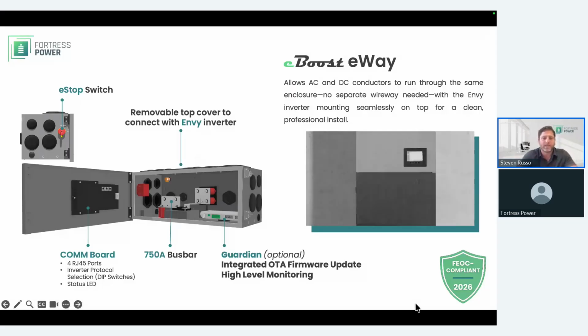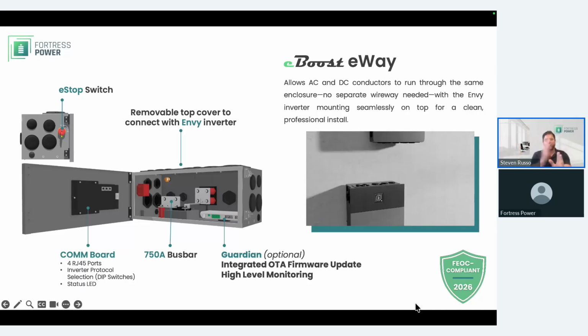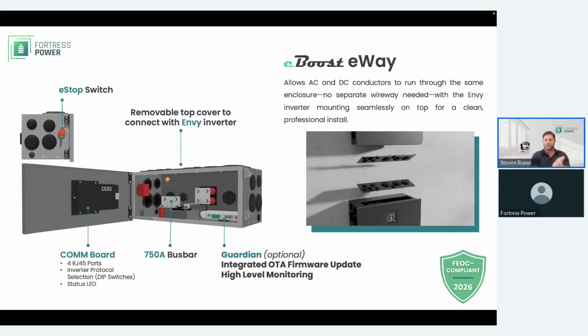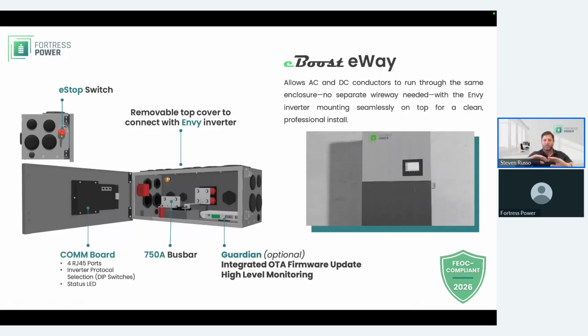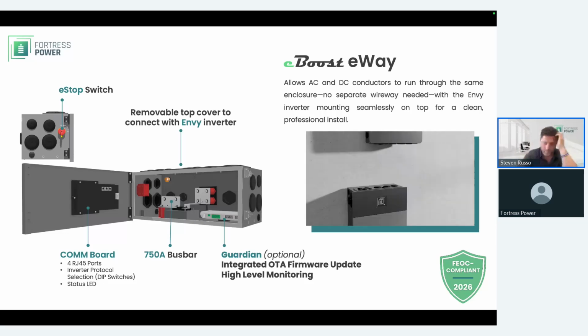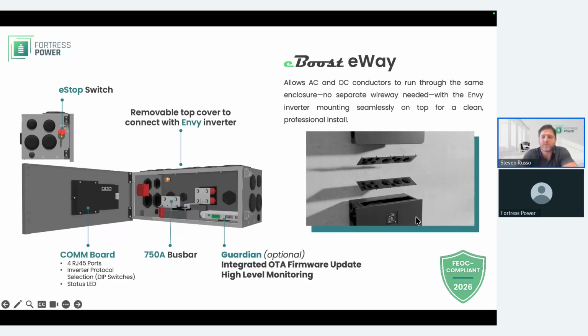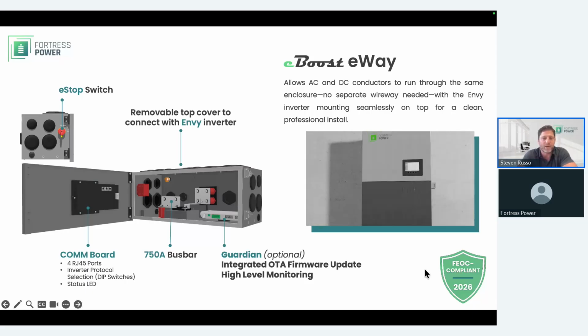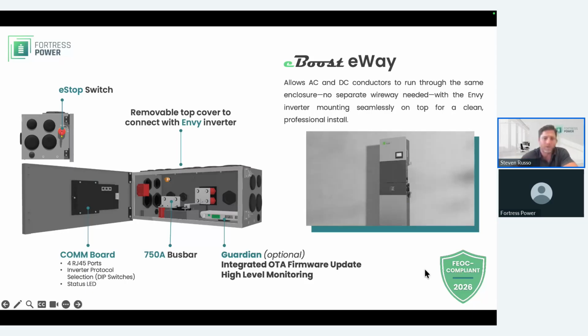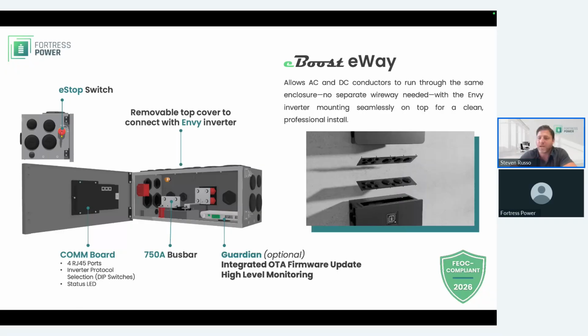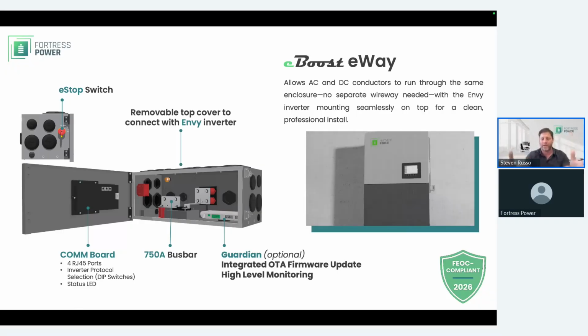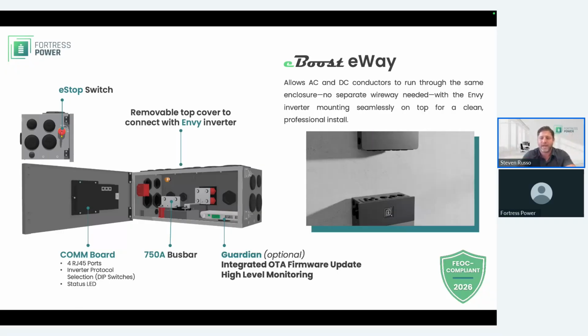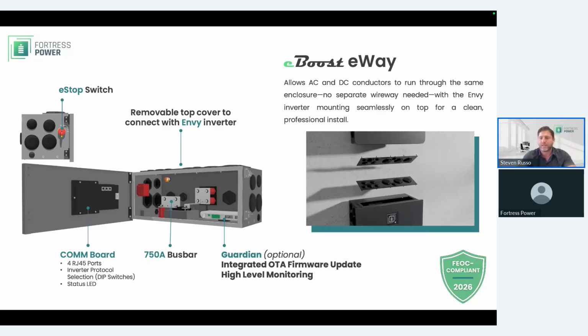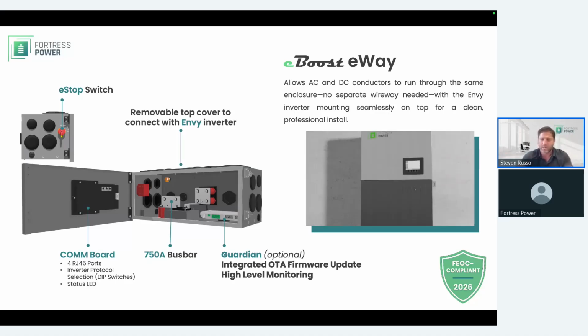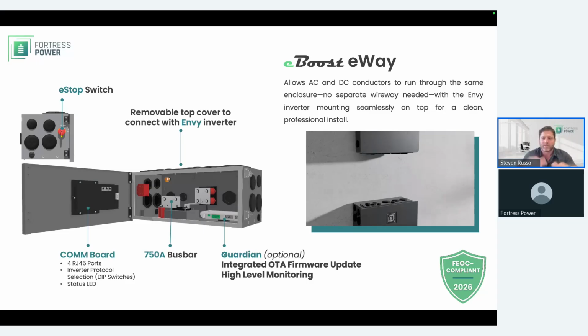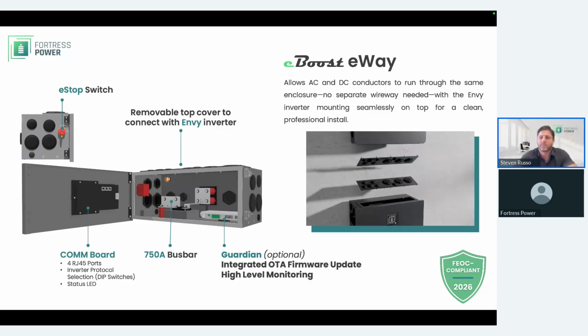It does have an opening, but it opens a little differently - it opens from the side, whereas the eForce eWay opens from top to bottom. As you can see on the graphic, it's the same overall concept: just take off the covers and have the Envy inverter stack right on top of the eWay, with no outside wiring, just one singular vertical system.